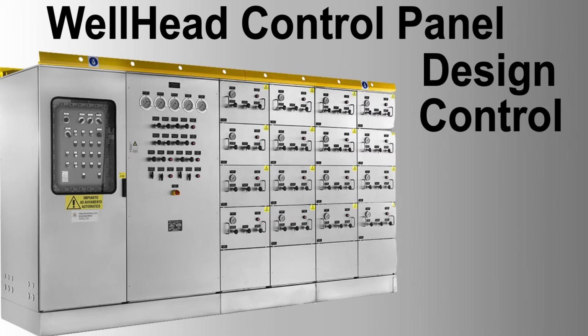2. Chemical injection control. Function: regulates the injection rate of chemicals into the well. Control device: dosing pump. Operation: the operator sets the injection rate. The pump runs at this rate without feedback on actual chemical concentration.